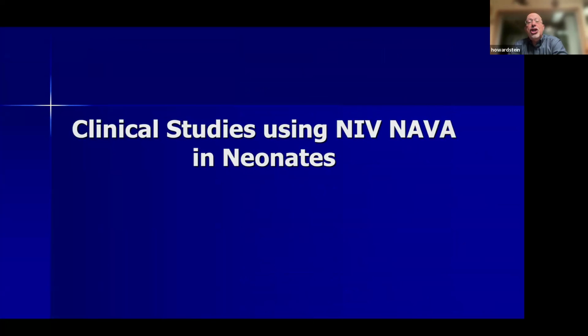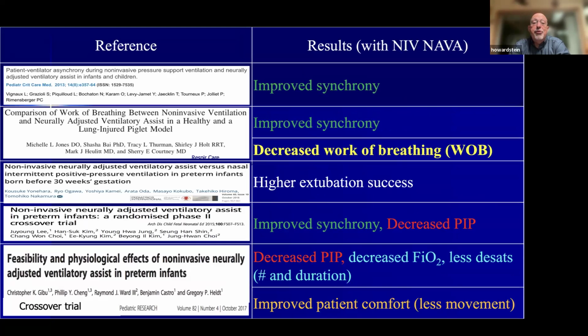Studies with NIV-NAVA show similar themes. Improved synchrony, and this is a big deal because with non-invasive ventilation, synchrony is very difficult. The enemy of the flow trigger is an air leak. But because we're detecting synchrony from the electrical signal in the diaphragm using these electrodes, air leak is not an issue. So even with a 100% air leak, as in that first slide that I showed you, that first little video, we are still able to achieve excellent synchrony.